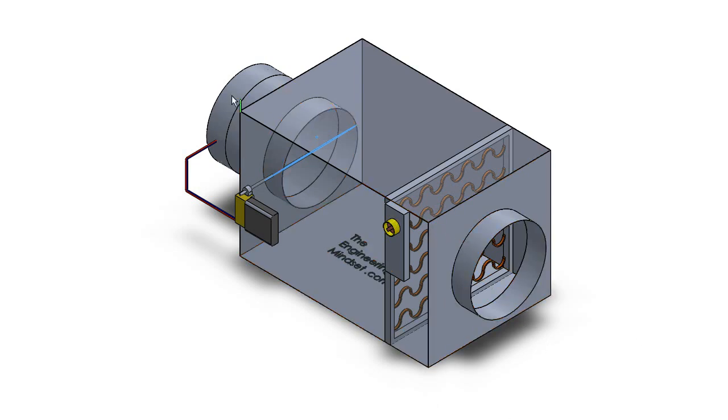The air entering the box, like I said, is around 13 degrees Celsius or 55 degrees Fahrenheit typically. But this temperature can be adjusted via your BMS. Sometimes that isn't warm enough. So we've got an electrical reheater here, which will switch on. And it will then just warm that air up as it passes through.